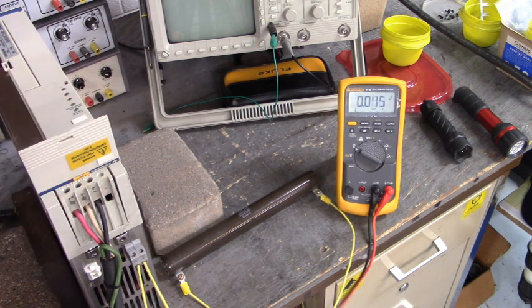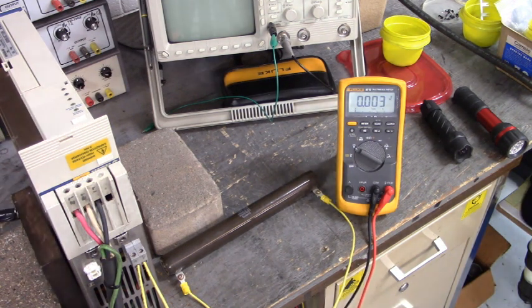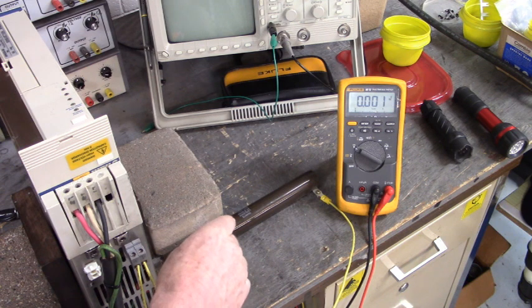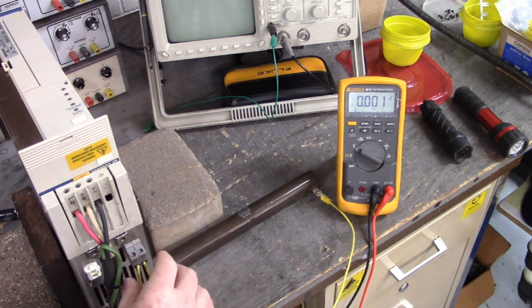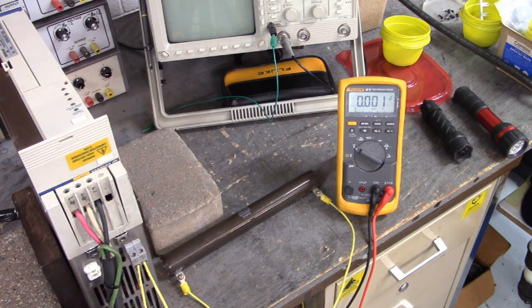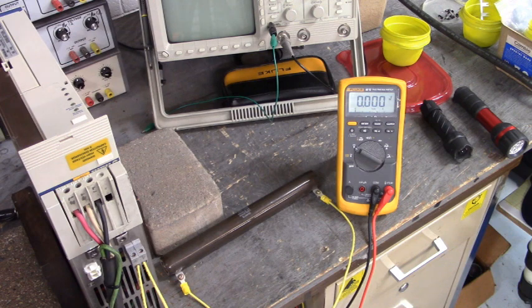There you go. So, if you're ever wondering why your contactor doesn't energize when you have this powered up on your bench, take a look to see if you have a regenerative braking resistor connected to this gray connector right here. That's the secret. In the machine you wouldn't have to worry about it because it would be connected, but out here on the bench you have to connect a resistor there. Otherwise you won't have any DC bus voltage out there on these terminals right here. So at the end of the video I'll put up the connections and you'll be able to test your new bus power supply.